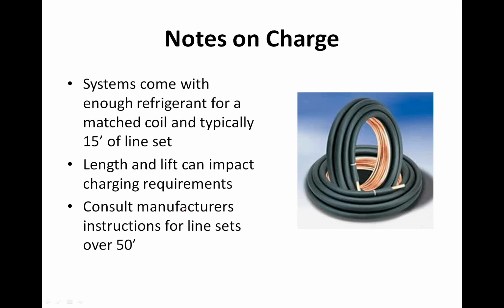When we talk about charge, systems come with enough refrigerant for a matched coil and typically 15 feet of line set. This is one of the big reasons that systems are not charged properly. We've got all these guys out doing new construction work, and a lot of times new construction is done off-season, and nobody ever comes back to check the charge on a system unless somebody calls and complains, right? So the system gets put in.